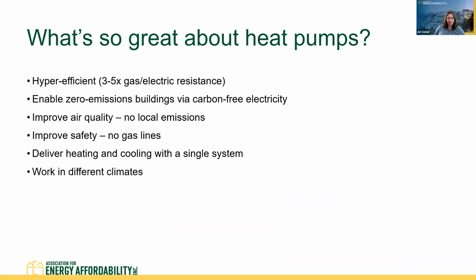What's so great about heat pumps? Well, they are hyper efficient. So they're 3 to 5 times as efficient as gas or electric resistance equipment. And this is really because the electricity is not being used to heat the water directly. It's just being used to run the compressor that is moving heat from place to place. So we can get very high efficiencies here.